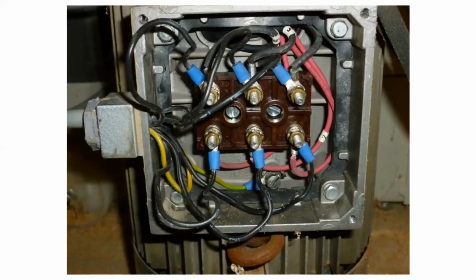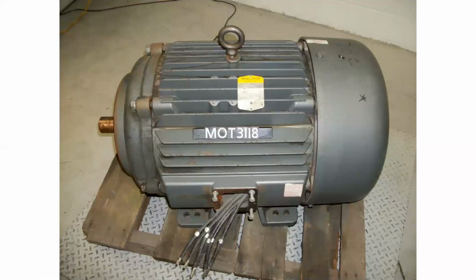This is what the connection could look like within the terminal box, although often this is more of a European type of motor where the terminals are insulated and provided a secure backing in the terminal box itself. More often we have motors like this, which we've seen a few pictures of already, which have the individual leads identified T1 through to T12, and we make our connections in the terminal box.